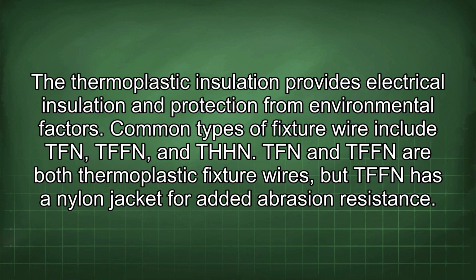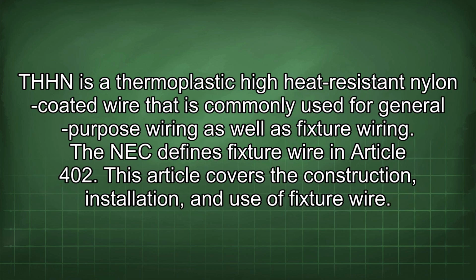Common types of fixture wire include TFN, TFFN, and THHN. TFN and TFFN are both thermoplastic fixture wires, but TFFN has a nylon jacket for added abrasion resistance. THHN is a thermoplastic high heat resistant nylon coated wire that is commonly used for general purpose wiring as well as fixture wiring. The NEC defines fixture wire in Article 402.